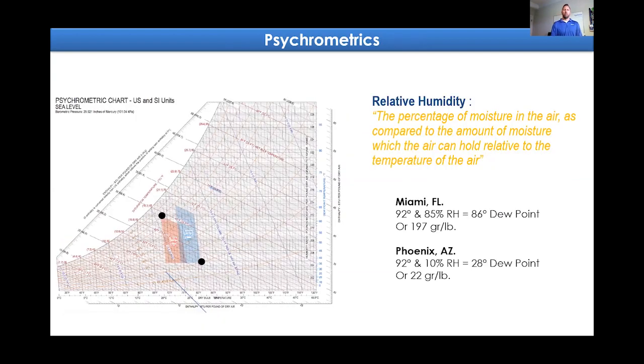If I get a little more technical and show you this psychrometric chart, you'll see it breaks down all the elements of air quality, representing temperature, humidity, total BTUs, grains per pound—the list goes on for what this chart tells us. But relative humidity, and why we use it often, is easy to understand because it's the percentage of moisture in the air versus how much it can hold at 100%.